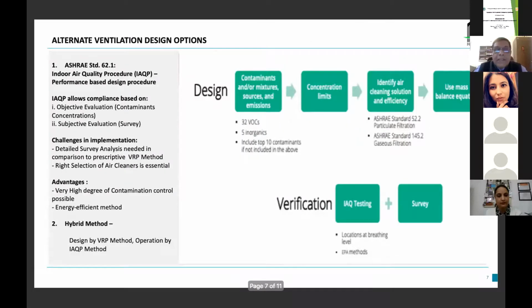So to implement this equivalent clean air approach, there are certain alternative ventilation design options which can prove to be effective. One of them is the ASHRAE Standard 62.1 indoor air quality procedure. ASHRAE prescribes both methods: the ventilation rate procedure, which I explained a few slides before, and the indoor air quality procedure, which is the performance-based design procedure. In the IBC, we have the prescriptive approach and the performance approach. So here also, the ventilation rate procedure is the prescriptive approach and the performance-based approach is the indoor air quality procedure.